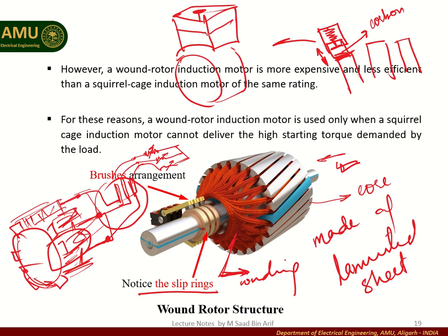Inside it we have the carbon material brush, and here we have a metallic capping of it. That terminal is attached with that metallic capping and the external circuit, and in between them we have a spring that pushes the brushes continuously on the surface of the slip ring.